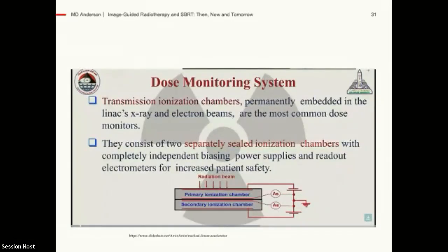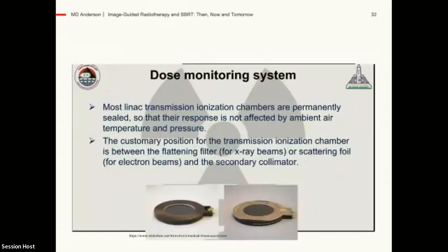So there's a whole dose monitoring system that utilizes transmission ionization chambers, permanently embedded in the LINAC. They're verifying, on any given second that machine is on, that it's delivering the dose rate and doses expected, and give a warning and shut it down before it gets out of tolerance. So there are so many feedback systems, and this is what those detectors look like, to make sure that whole LINAC is operating the way you expect.